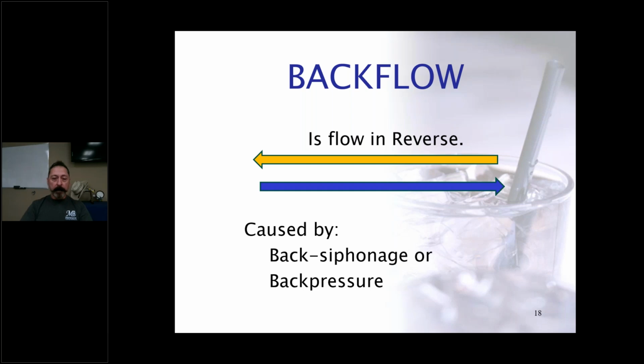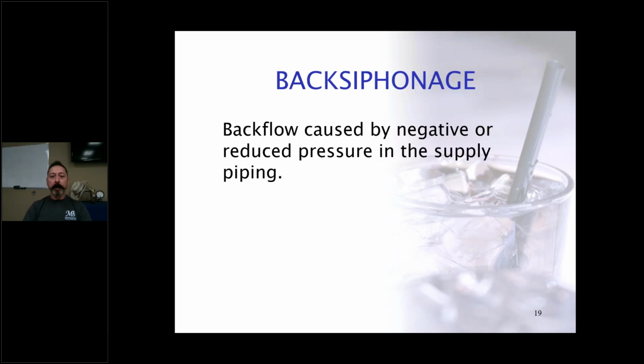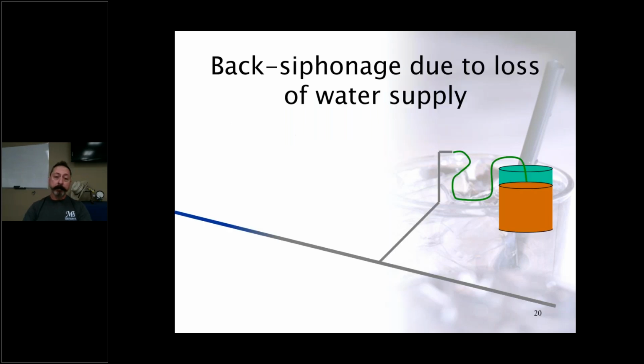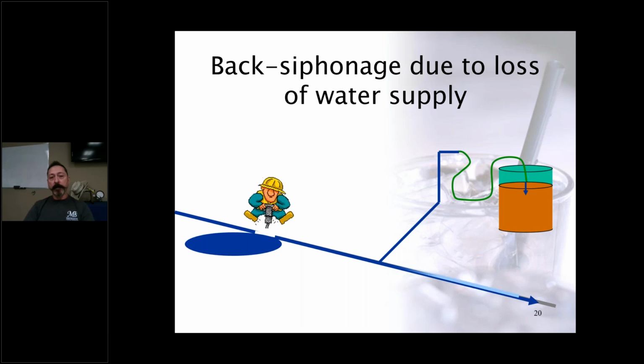So backflow is just a hydraulic term, meaning flow in reverse, caused by backsiphonage or backpressure. Backsiphoning is caused by a negative or reduced pressure in the supply pipe, causing a vacuum. So these can occur in two ways. You can have a backsiphon due to supply pressure loss or loss of supply due to a water main break, where everything just drains from the cross connection through the facility, through the service connection, and into the water mains. So that's just straight backsiphoning from an upper elevation to a lower elevation that are both open to atmospheric pressure.